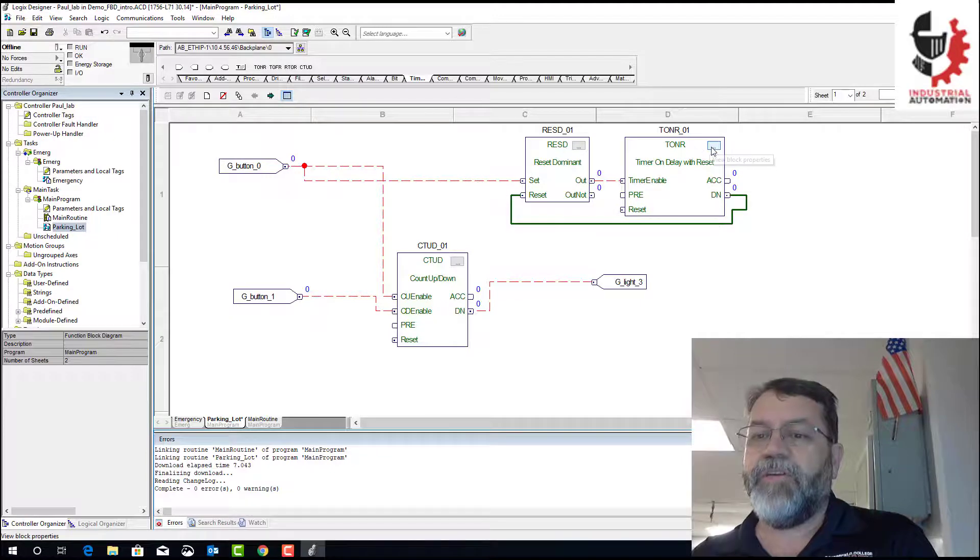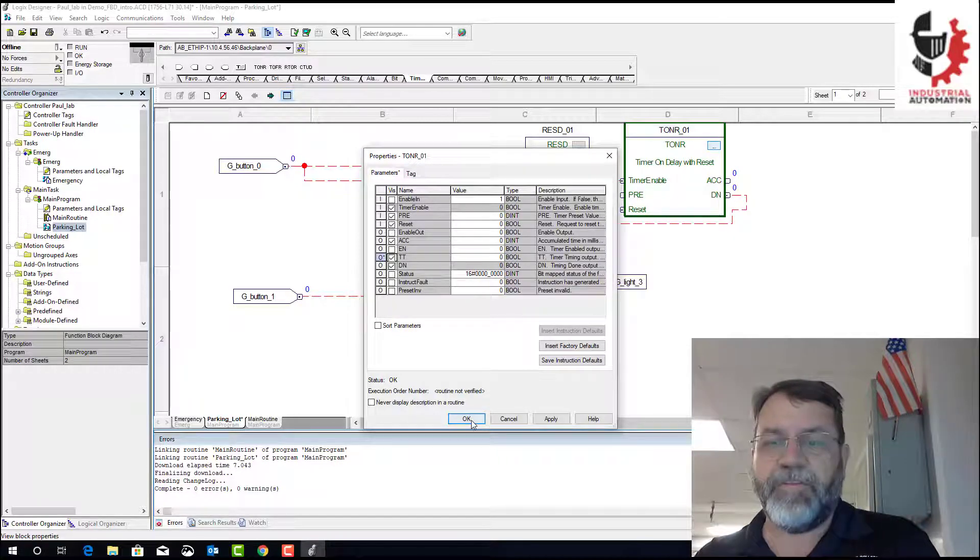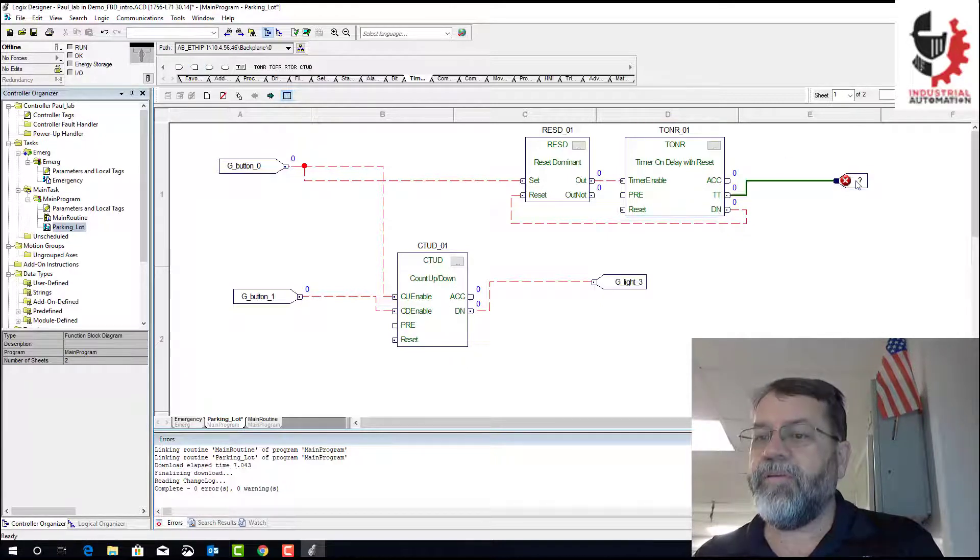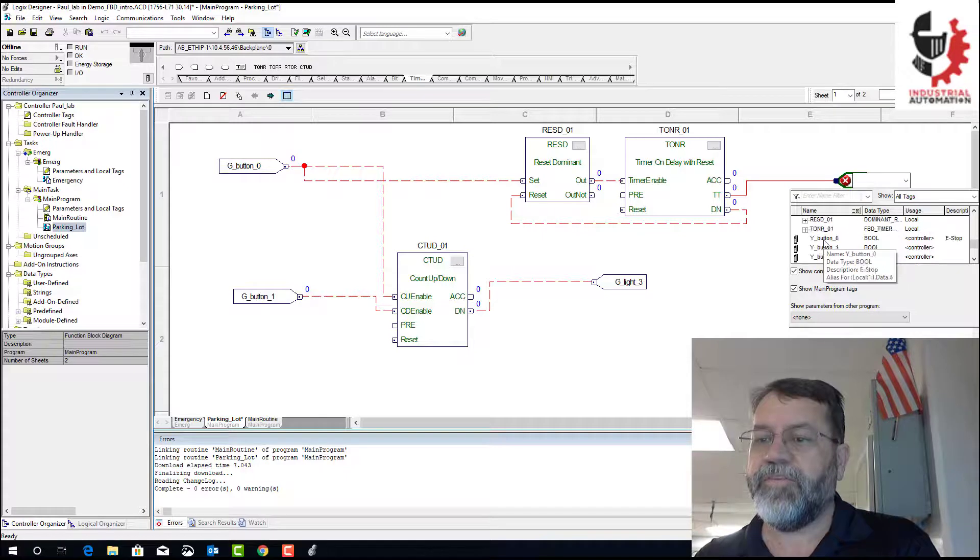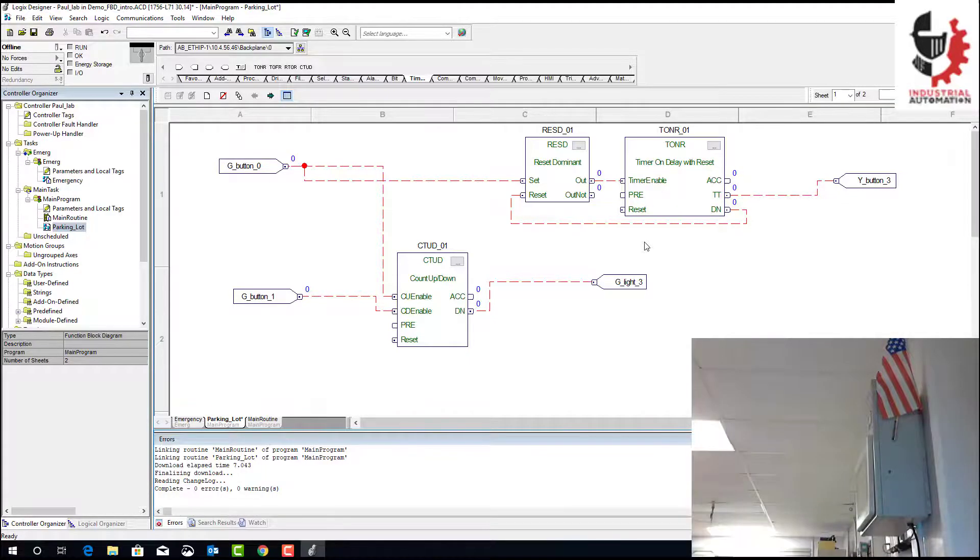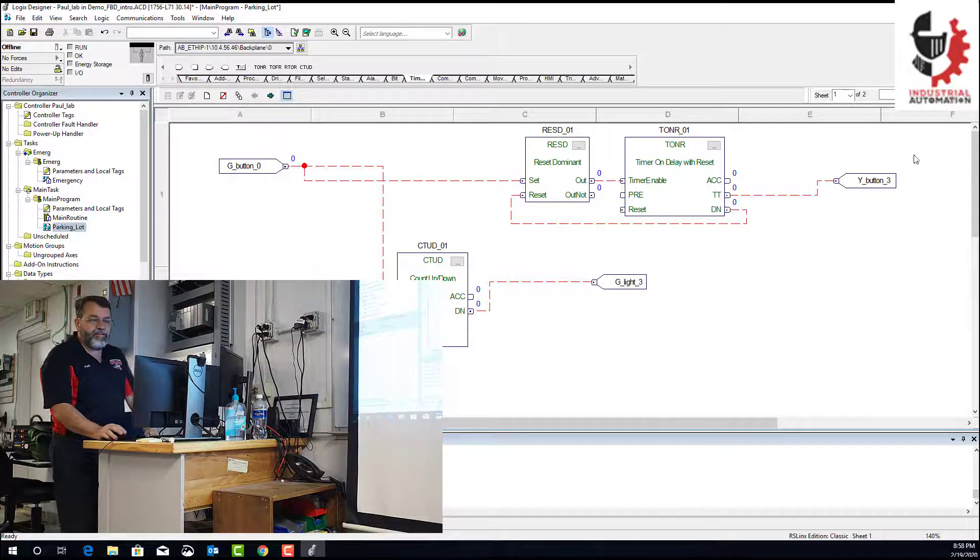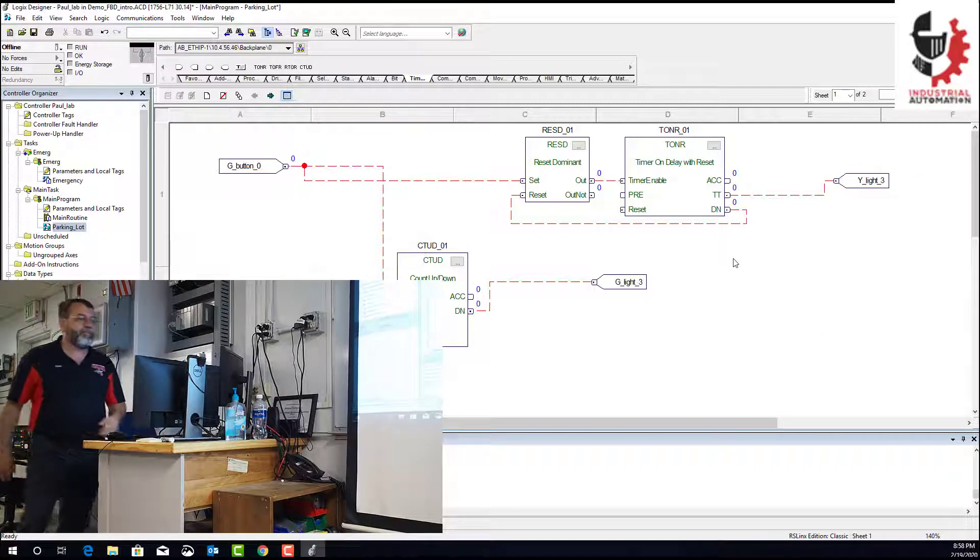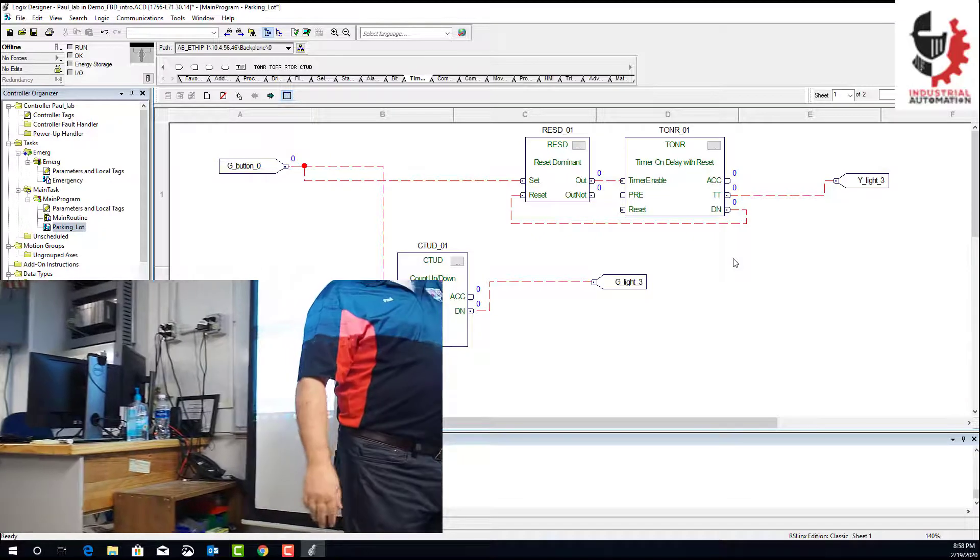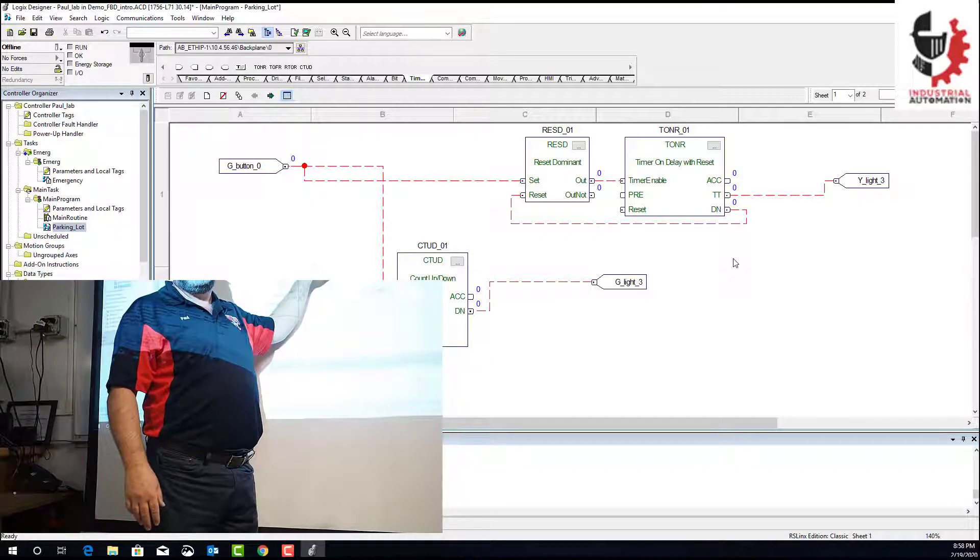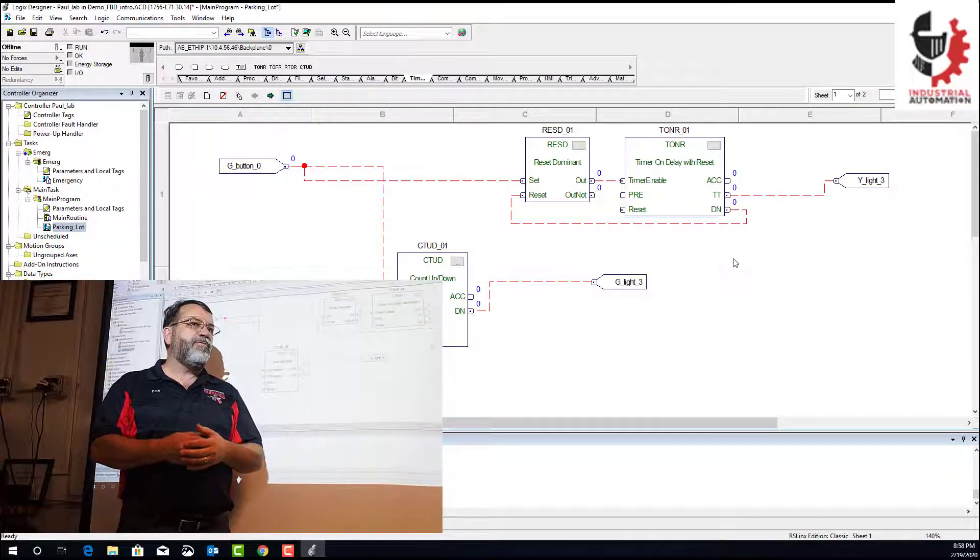Then what I want to do is I want to reset this guy after my timer finishes. So I can go from this done bit, and I can go back around to reset. So that will reset the timer after it finishes. Now I want to use timer timing on this function block, and I don't have it, right? I've got accumulate and done. When I click on the little gray box, it brings up all the options, and I can turn on timer timing. Now I've got my timer timing, and I'll hook that to a light. I'll go green light, I'll go yellow light four, how does that sound? Or three. Oh, I did button. Now, I've got this reset dominant to seal it in, so as soon as I get a signal, it's going to lock in, it's going to start this timer. When that timer's done, it's going to send a reset back to this guy.